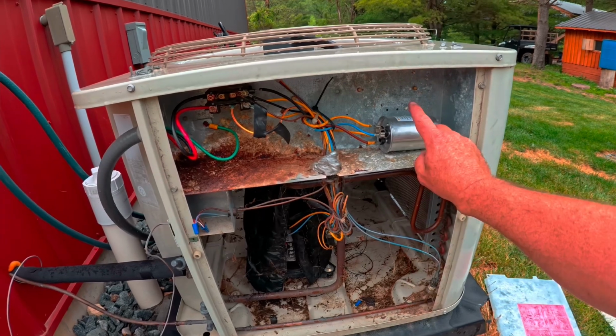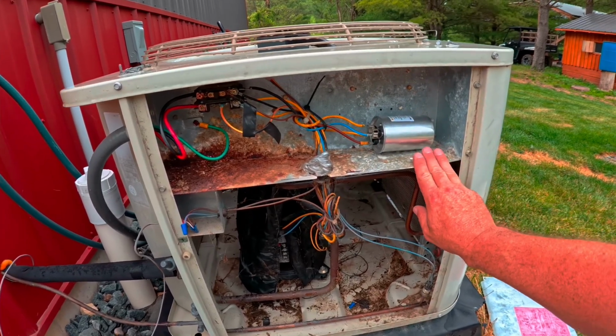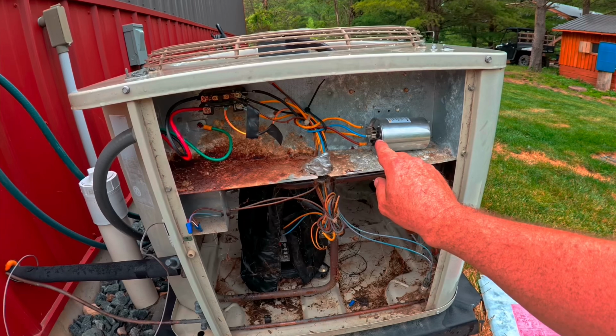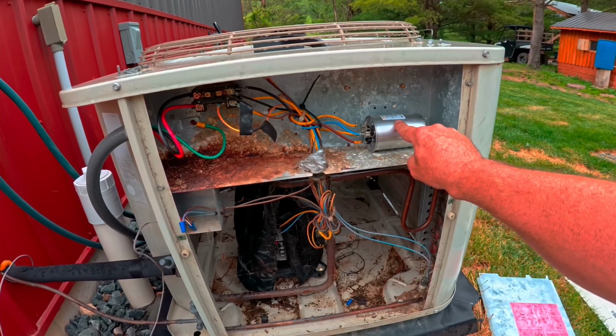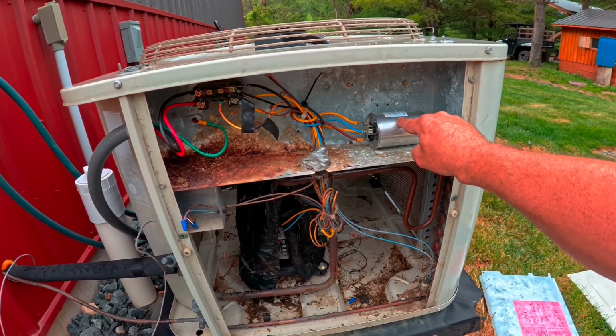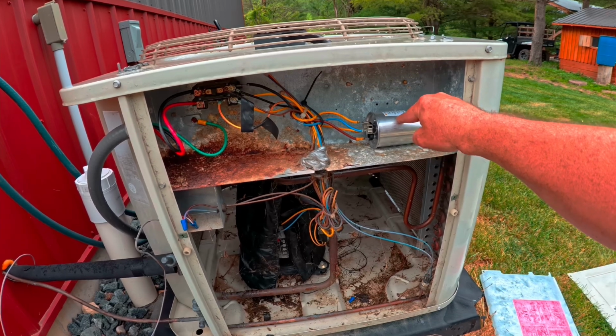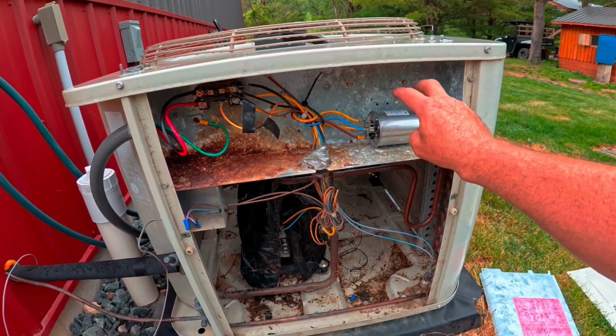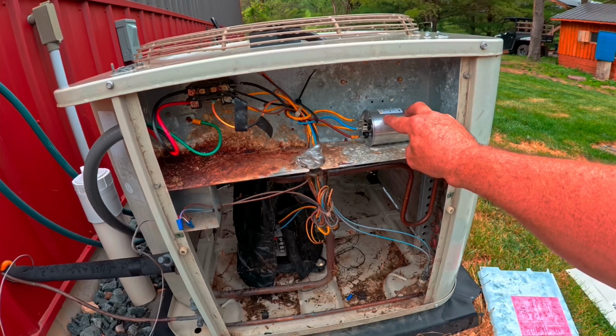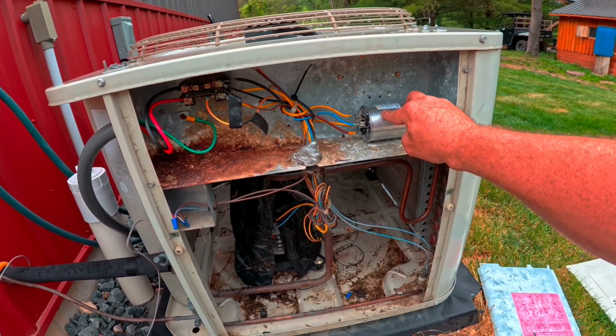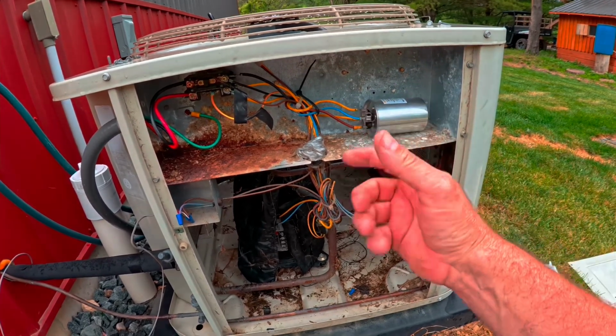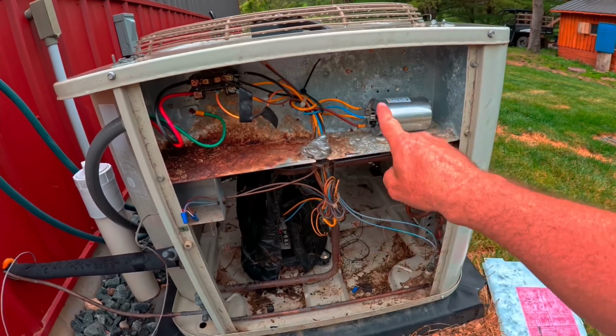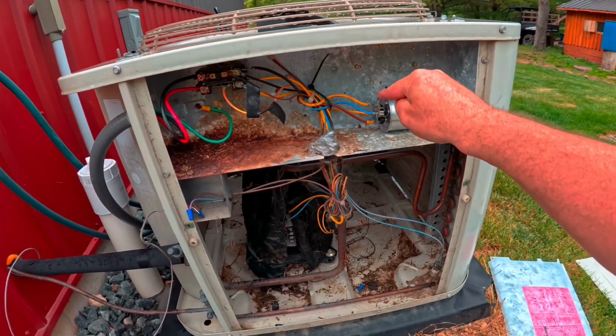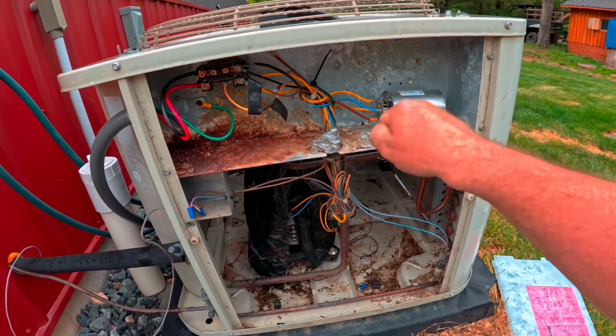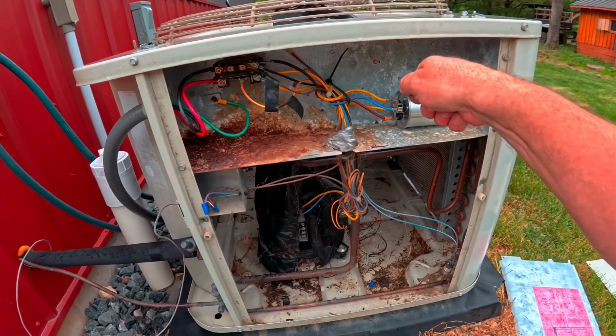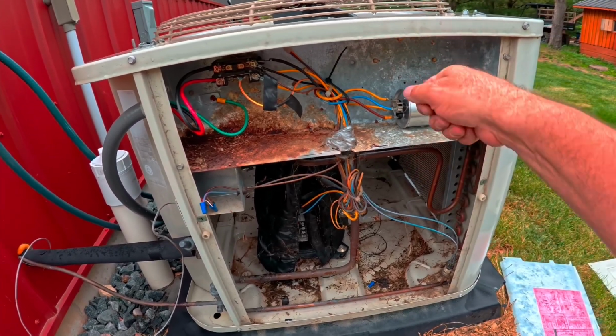Number 2, before you touch any of these wires, I don't care if the power is off, do not touch these wires. You need to discharge this cap. Like I said, this runs the fan and the compressor, so it might not be starting one, but the other side's still charged. So you need to discharge the capacitor. The proper way to do that is to basically take a metal screwdriver with an insulated handle, and you need to short the terminals between each other as much as you can. Short the terminals to chassis ground, which is just metal.